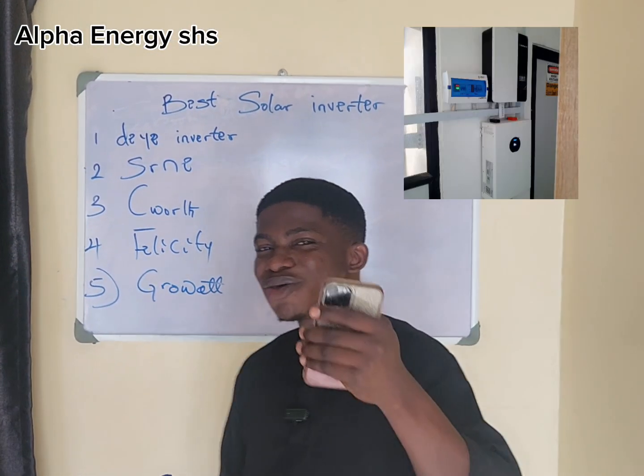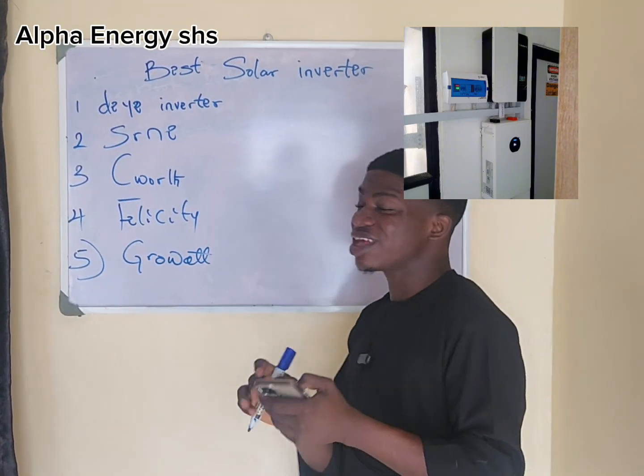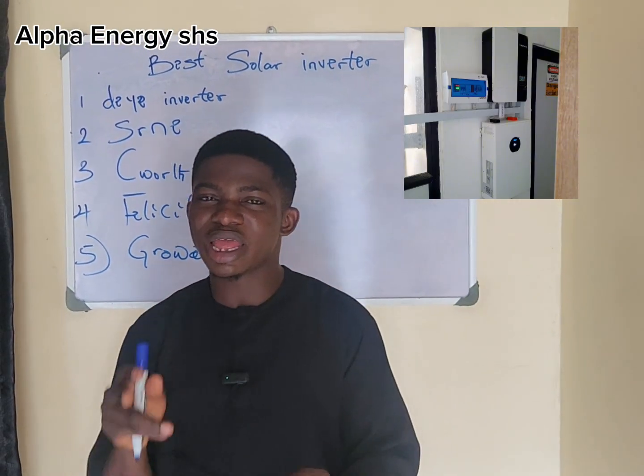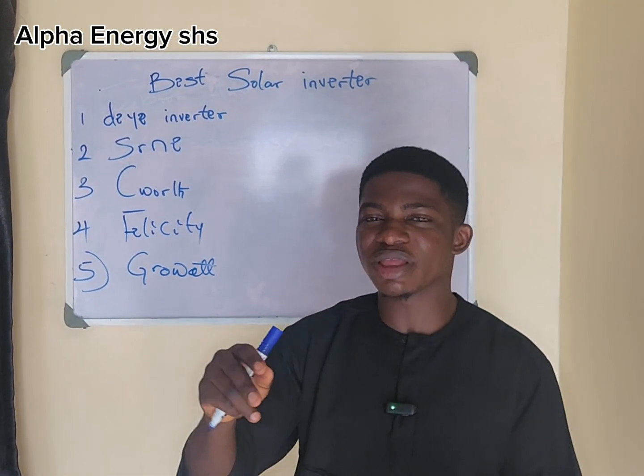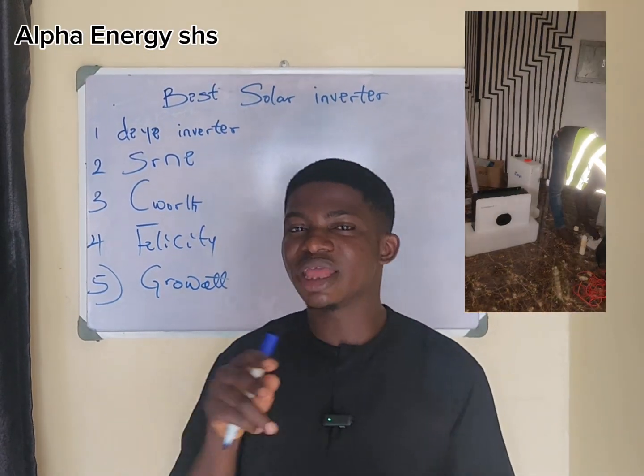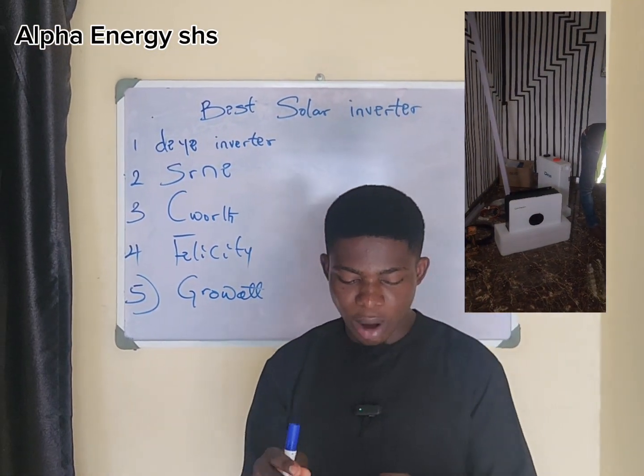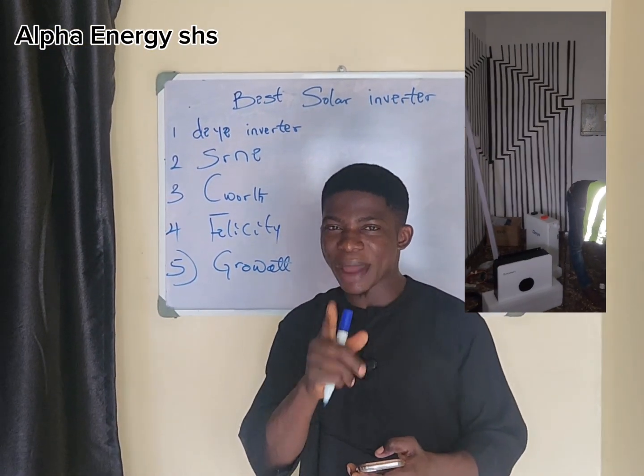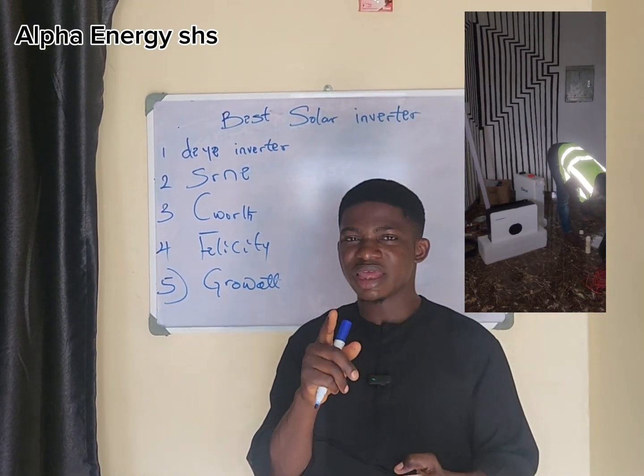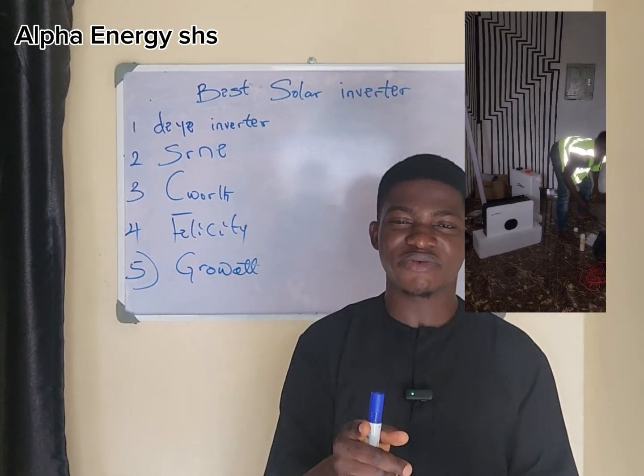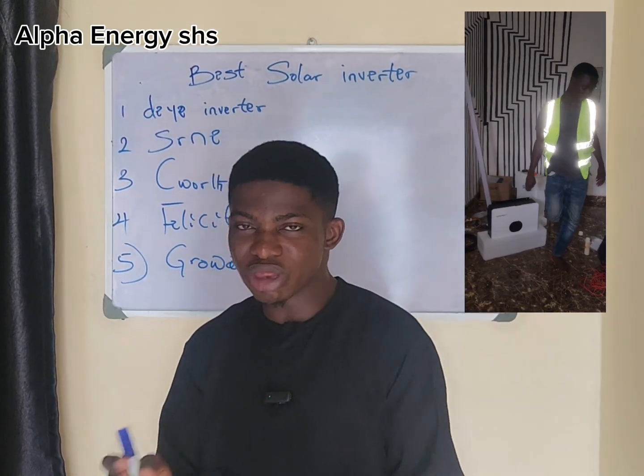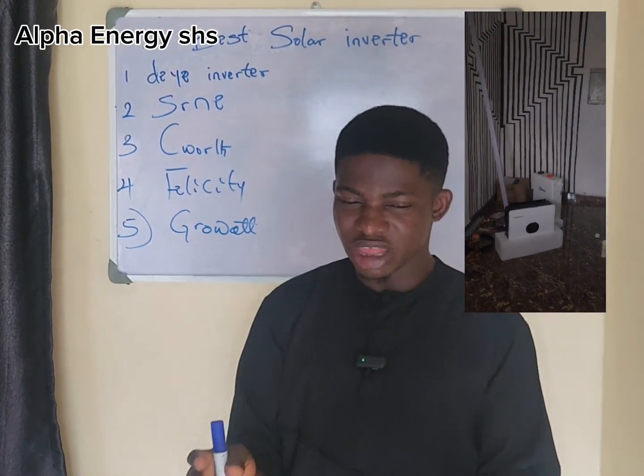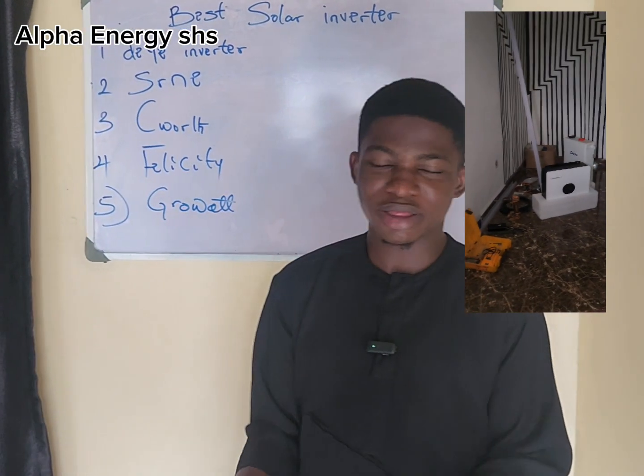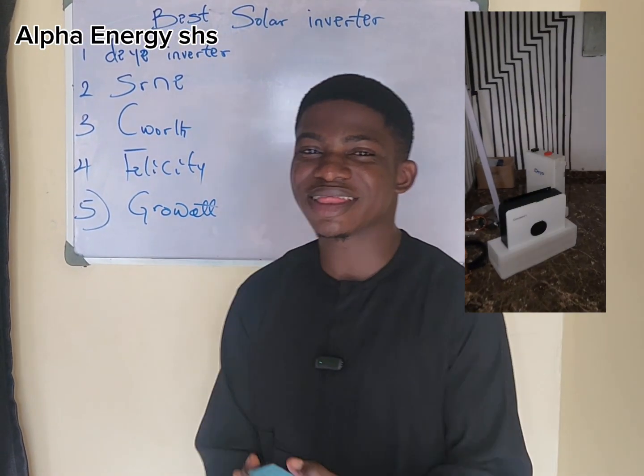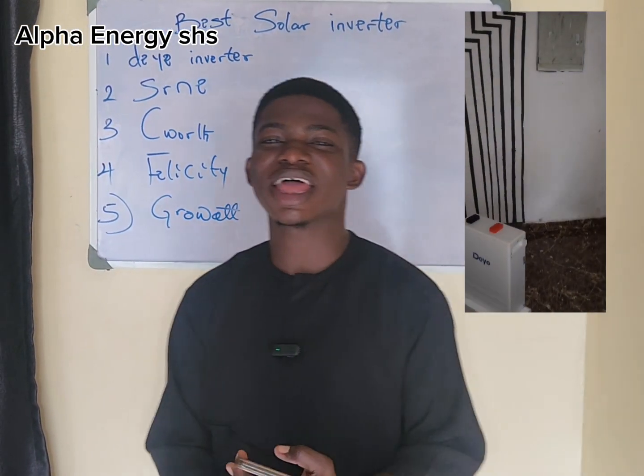Now, there was a day this Growatt inverter showed me shaggy. I was in the client's house installing a 6 kVA Growatt inverter with a 5 kilowatt DA lithium battery. At that point, I didn't know about pylon, that there's a setting called pylon on Growatt inverter. I tried communicating these two systems. They were not communicating. I just left the inverter set on user defined, and I left the place.